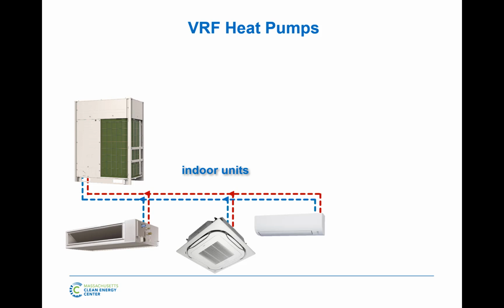Let's go through the components a little bit. Again, the indoor units, there's all sorts of different types. The concept that air source heat pump is a wall-mounted type of unit is also an older thought. About 50% of the VRF market uses ducted units, whether it's horizontal, whether it's vertical, whether it's console. Greg later will go through all the different types of indoor units that you can have in the VRF world. We do have the wall mounts that you're used to, those wall mounts up high wall units. There's cassette type units. There's all sorts of different indoor units.